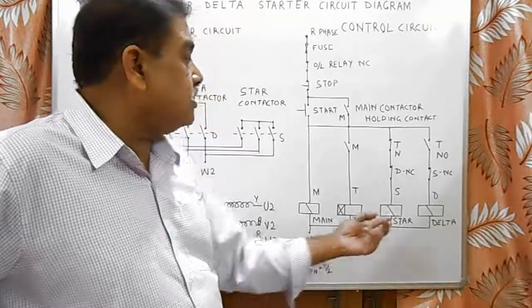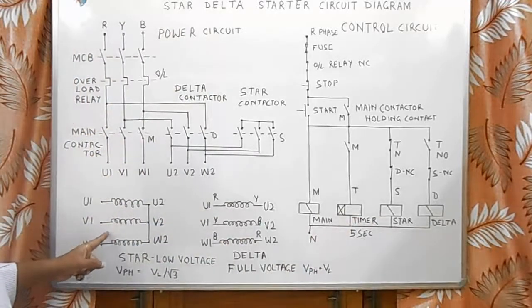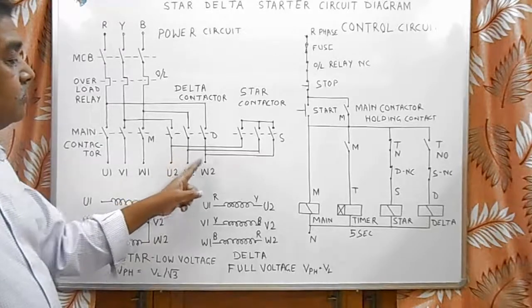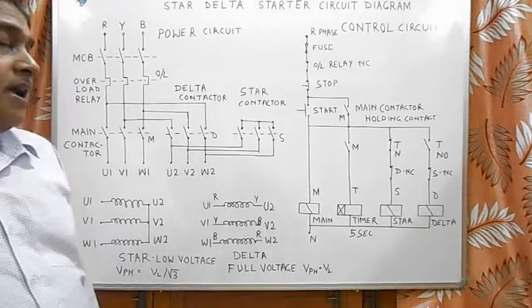As soon as M and S contactors pick up, main contactor gives supply to the three-phase winding and star contactor short-circuits U2, V2, and W2, and motor starts running in star connection.